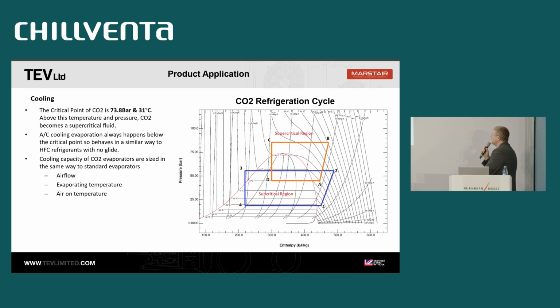So next, in terms of the application on the cooling side, there's a typical transcritical and subcritical graph. Obviously, we have the critical point, which is 31 degrees for CO2, 73.8 bar. Above that, you're in the supercritical zone. But for cooling, everything is on the subcritical side. So the way you apply it is very similar to the way you would apply evaporators for cold rooms, in terms of the way you size them.